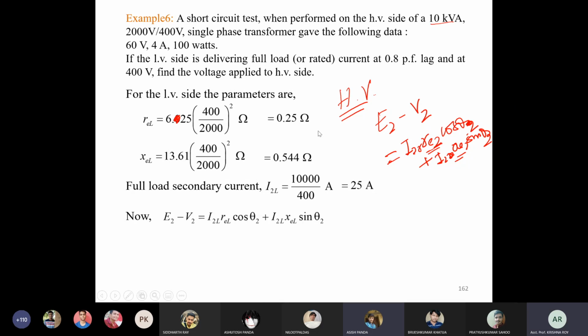Now E2 minus V2 equals I2L, the rated current, into REL, because the low voltage side is the secondary side, cos theta 2, and for lagging power factor this will be positive, plus I2L XEL sin theta 2. For cos theta 2 of 0.8, sin theta 2 equals 0.6. Put all those values in. The final value for E2 minus V2 is 13.16 volt.